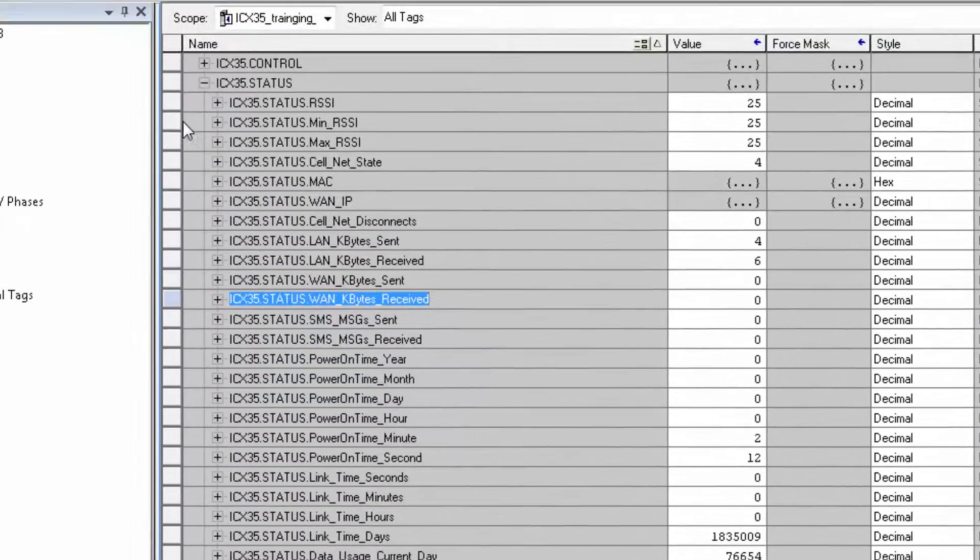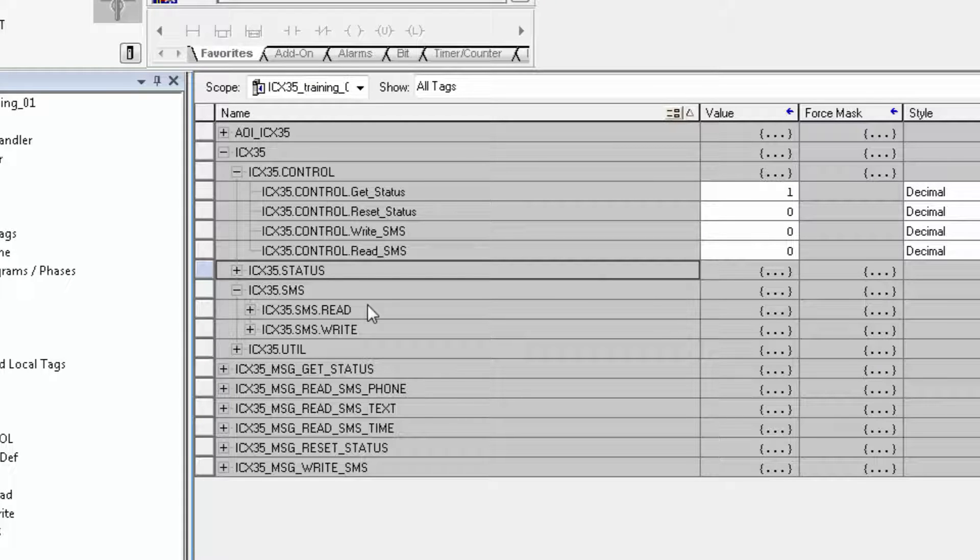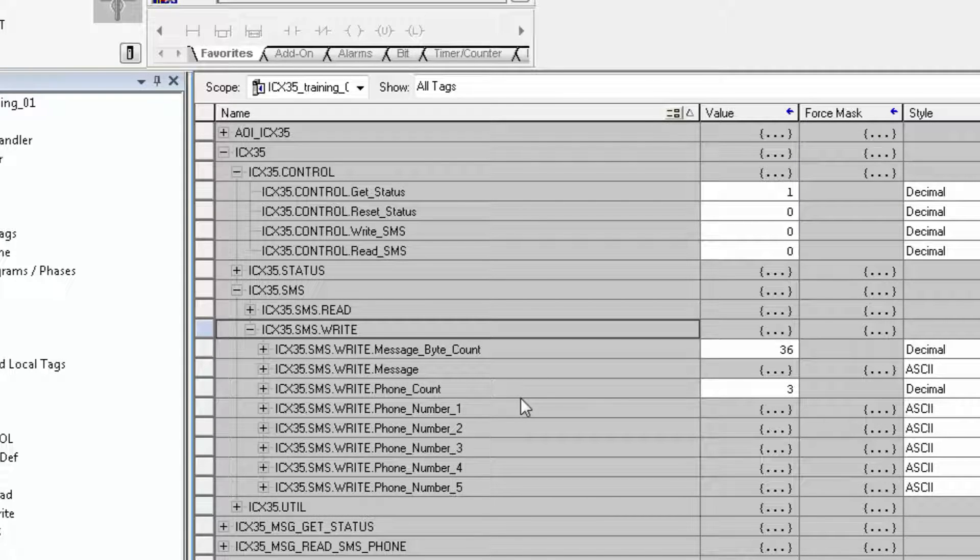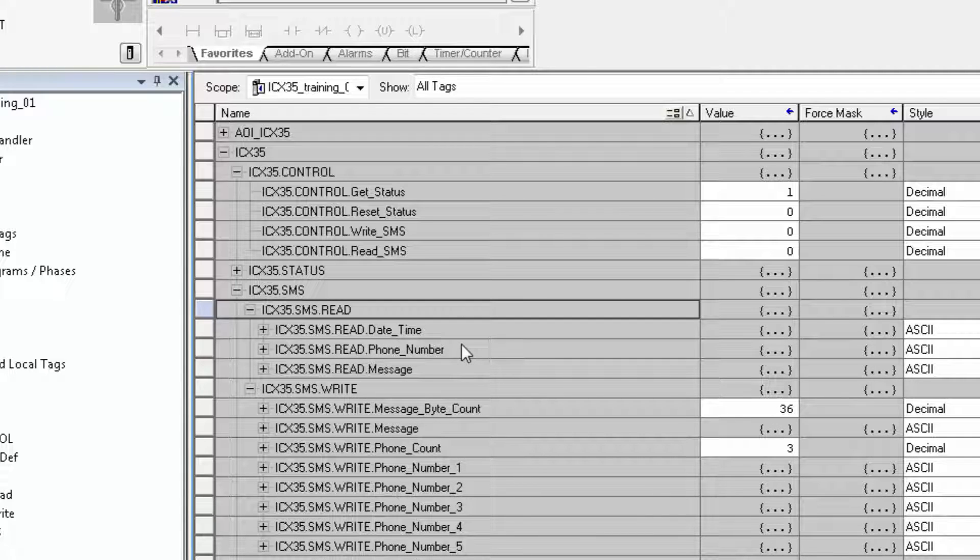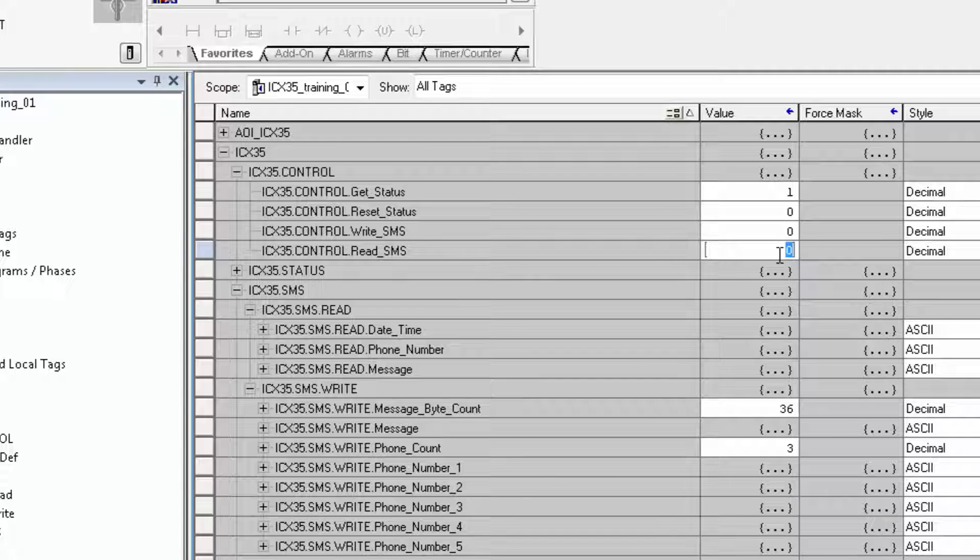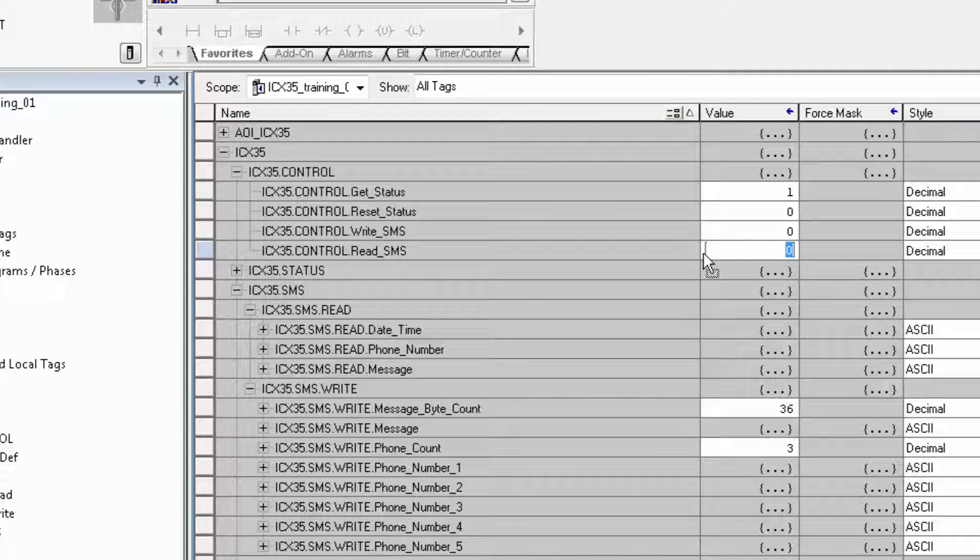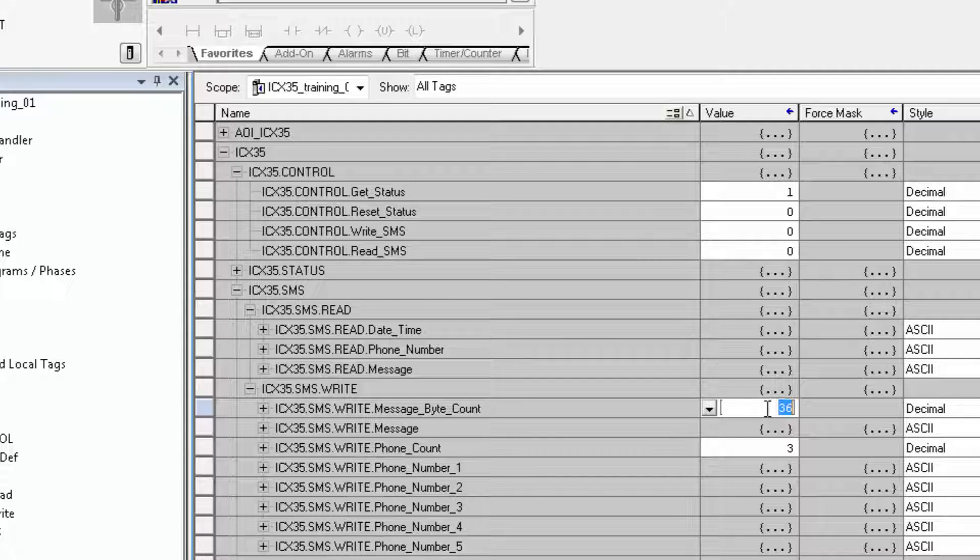Next, we'll go over SMS text messages. Expand SMS and here are the SMS read and SMS write tags. To send text messages to cellular devices from the gateway, you have to use the SMS write array. The SMS read array contains the SMS text messages received by the gateway from cellular devices. When the control trigger for the SMS read is toggled, you will see the most current text messages in the ICX35's buffer populate the SMS read tags. The message byte count shows the number of bytes allowable in the SMS messages. 160 is the standard limit.